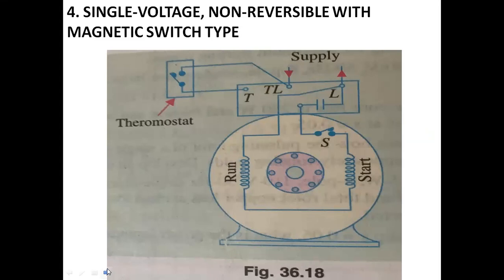I am telling the connections. A bimetallic strip of thermostat is used. The terminals are T, TL, and L. T is one end of the thermostat, TL is the other end connected to the supply, and L is the point connected to the running winding, switch, and the capacitor. In capacitor start motors, these are used in refrigerators. Three leads are brought out from four terminals, marked as T, TL, and L. The thermostat is connected to T and TL, the capacitor is between L and the unmarked terminal, and the supply lines go to TL and L.